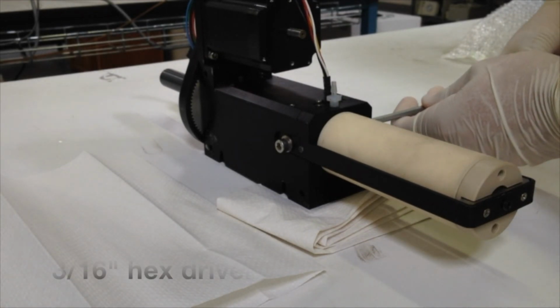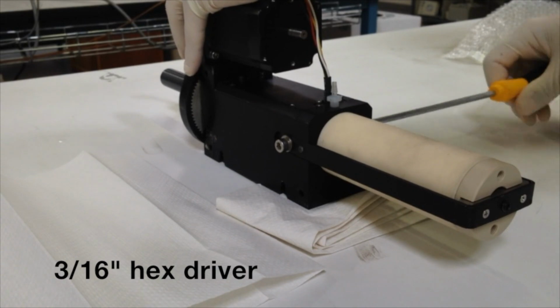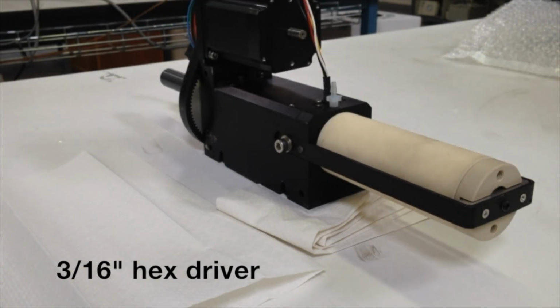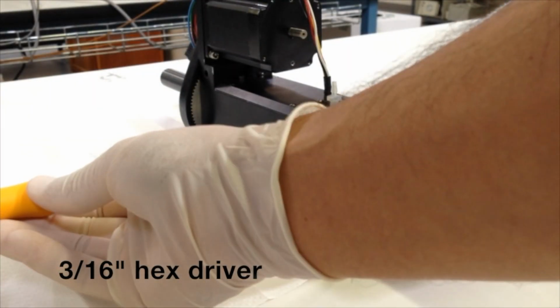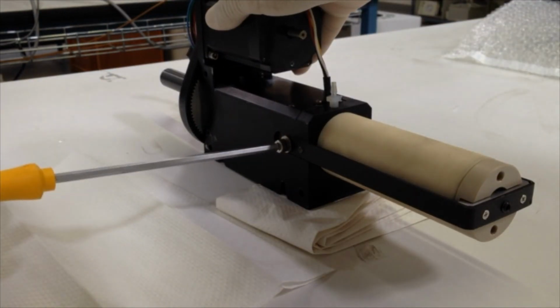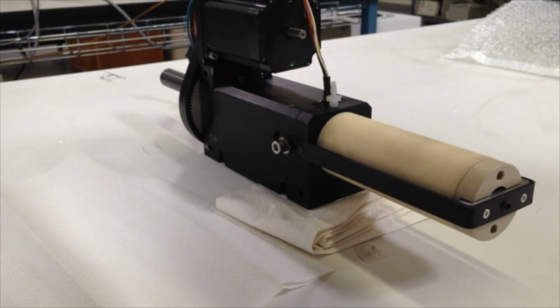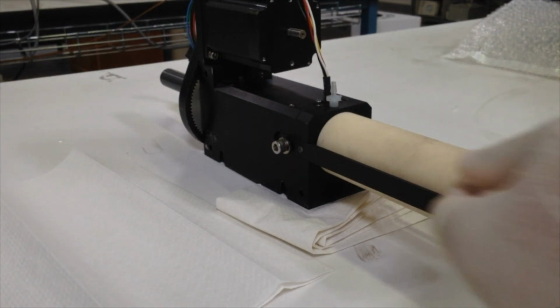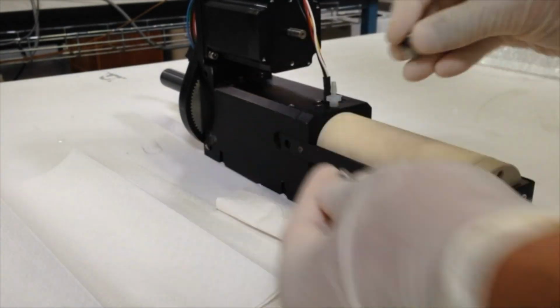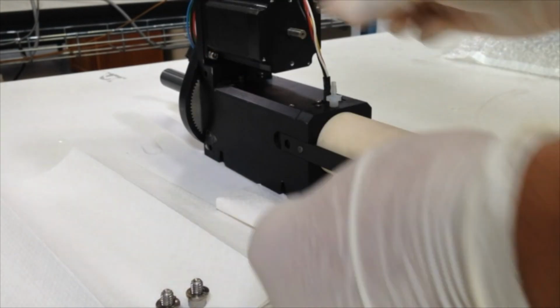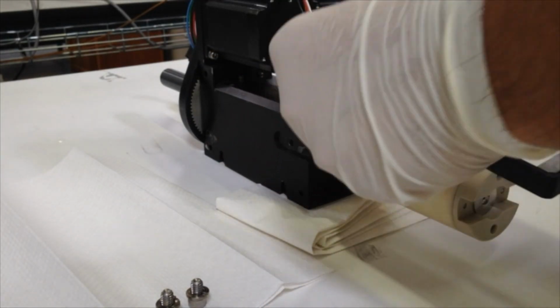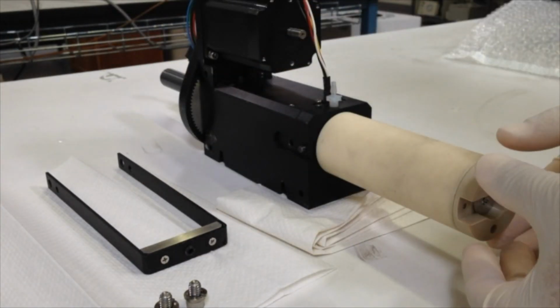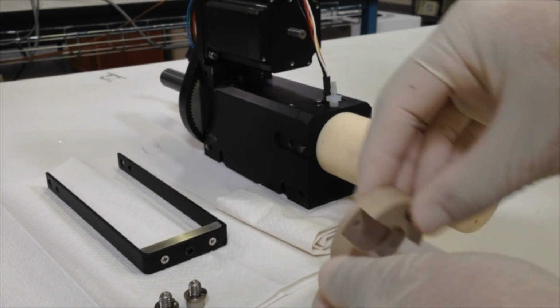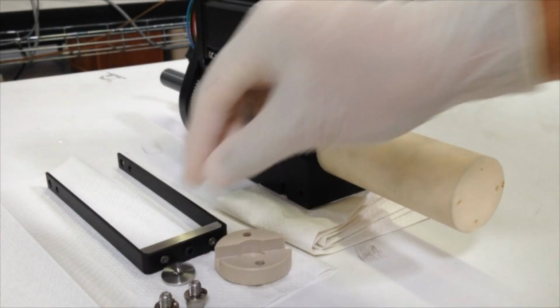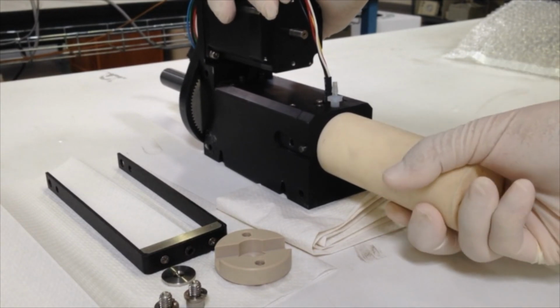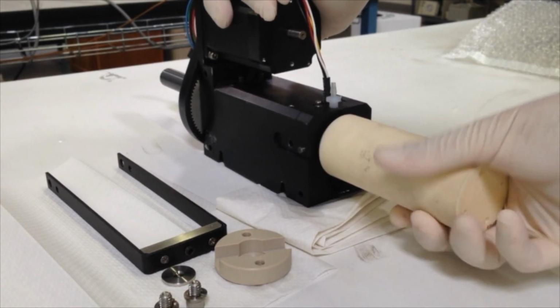Use a 3/16 inch hex driver to completely remove the 2 cap screws that hold the pump bracket to the pump body. Place a thick paper towel under the pump body to absorb any excess flush solution still in the cylinder. Pull the cylinder off by twisting in a clockwise motion.